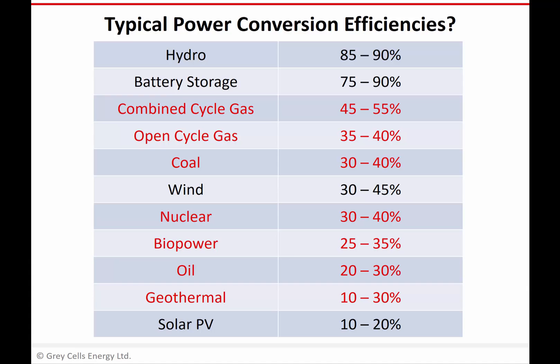With thermal power generation, another variable which alters conversion efficiency is the temperature of the input — the temperature at which the fuel burns, or in the case of something like geothermal, the temperature of the water extracted from the ground. If you start with a lower temperature, conversion of heat to electricity will be less efficient. That's why geothermal looks quite low on this chart — some sources of geothermal have relatively low temperatures, so conversion efficiency is also relatively low. But of course, with geothermal you haven't had to buy the fuel. With things like oil and biopower, it depends on the technology — some plants use large conventional steam turbines, others gas turbines, and some small generator sets using internal combustion engines at lower efficiency.